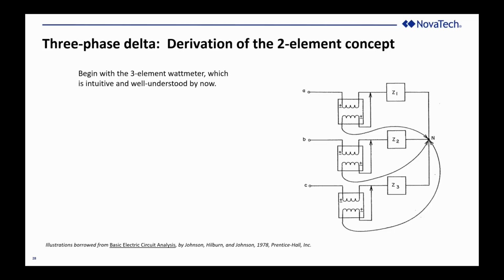So we start with something that we all agree is intuitive and well understood, which is the idea of a 3-element wattmeter. Notice that I've moved the neutral to the right of the 3 loads. That's arbitrary. I could just as easily have had the neutral at the bottom of the page with a conductor running back to the source. But the point is still the same. The voltage winding of every wattmeter goes from the line to the neutral point, and the neutral point for each of the 3 wattmeters is the same point. That's where we start. So this stands without further explanation as intuitive measurement of the total 3-phase watts.